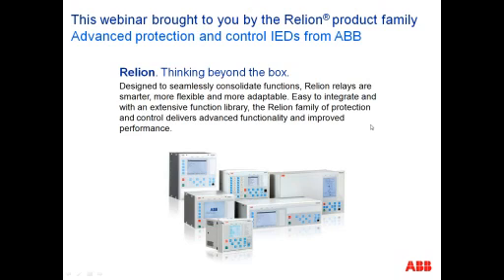Now, a low impedance method generally allows you to have an input. Let's call it a multi-restraining device. You have an input from each CT, but each CT input can be handled with an internal transformer or an internal transformer type calculation to allow you to use different CT ratios. And again, you put all the CTs on the same primary base and work at primary level quantities, if you will, in your calculations.